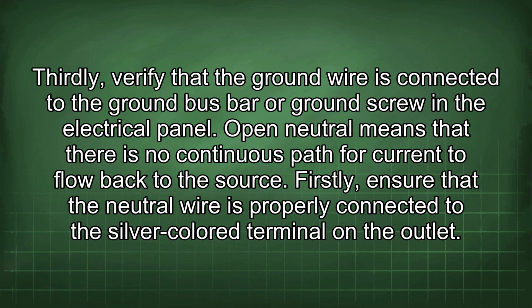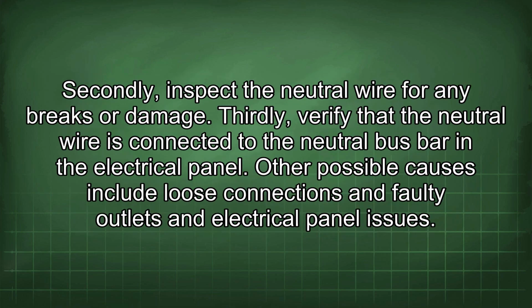Open neutral means that there is no continuous path for current to flow back to the source. Firstly, ensure that the neutral wire is properly connected to the silver-colored terminal on the outlet. Secondly, inspect the neutral wire for any breaks or damage. Thirdly, verify that the neutral wire is connected to the neutral bus bar in the electrical panel.